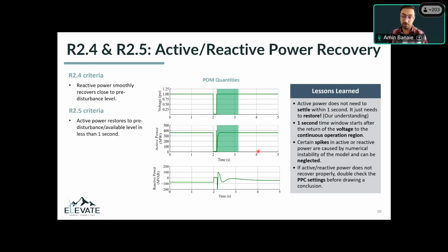So if active power goes from 0 to 1 and then it has some overshoots and it takes some time to settle, we consider that as a pass. And then another factor that is very important is that this 1 second time window starts after the voltage returns to the continuous operation region, which is 0.9 per unit, sorry. So some people, I've seen that in their studies, they consider this fault duration into this 1 second time window. As the standard clearly says, this 1 second starts after the fault is cleared.